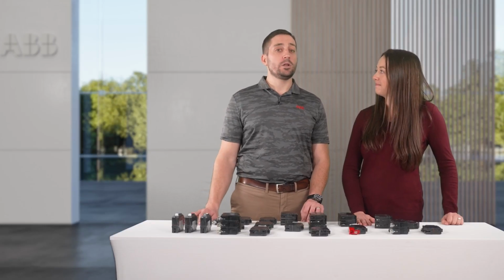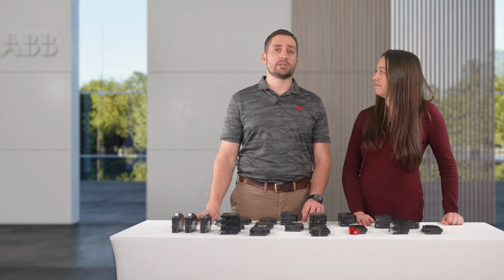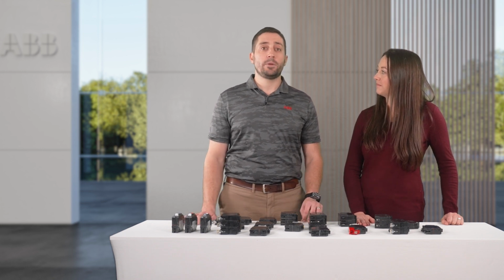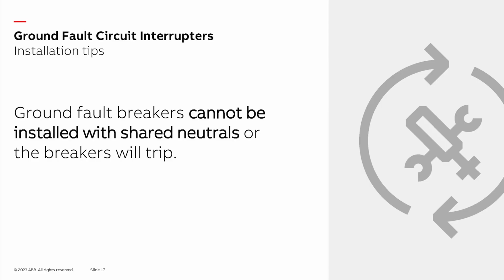Let me give you an example. If a hairdryer is dropped into a tub full of water, some of the electrical current leaks out of the appliance and into the water. This current leakage could be enough to kill someone who comes in contact with the water, but not large enough to trip a non-ground fault circuit interrupter. Thermomagnetic circuit breakers only guard against overloads and short circuits. They are not designed to protect people from electrical shocks. When installing ground fault breakers, they cannot be on a shared neutral or the breaker will trip.